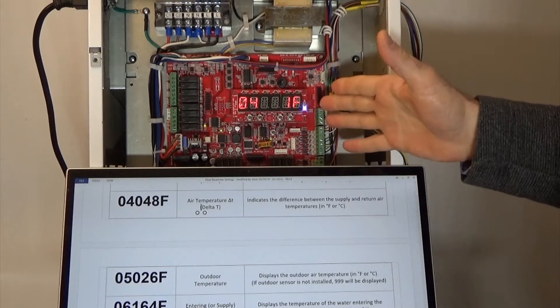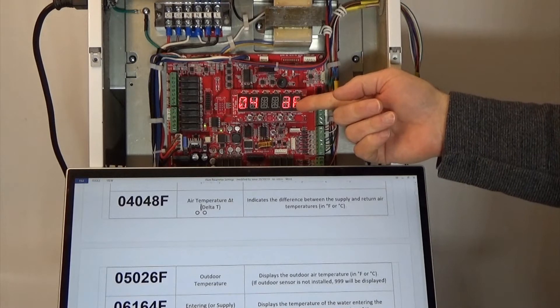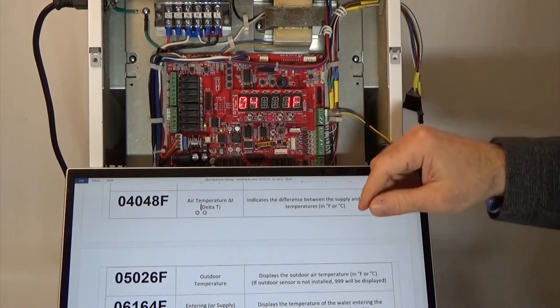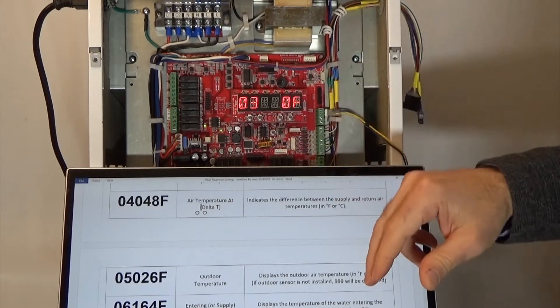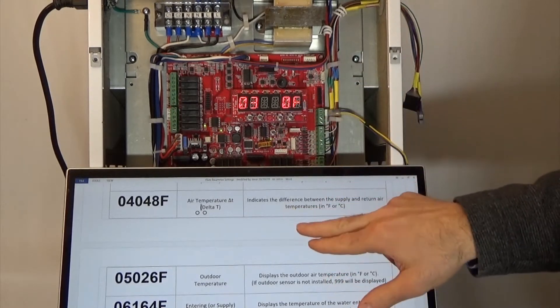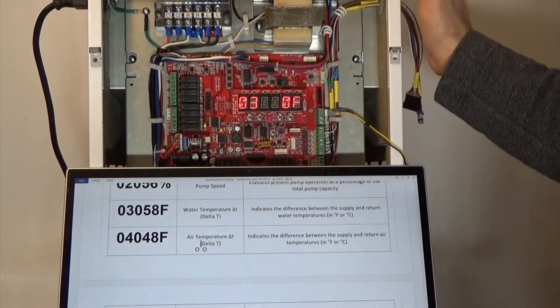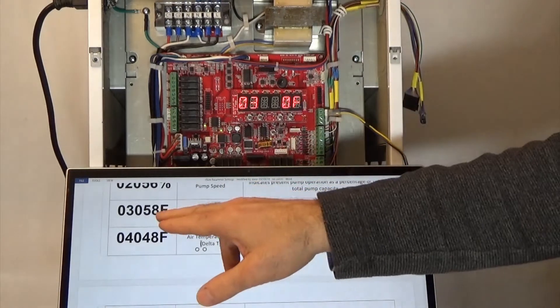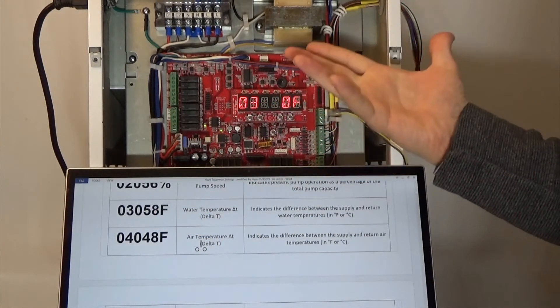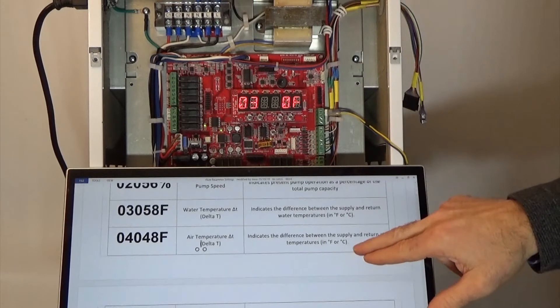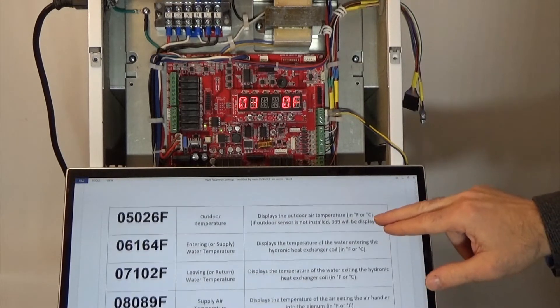Because this unit is off, it makes sense we're seeing zero here — zero differential, both sensors seeing the same number. If we go down to parameter three, same thing on the water side. Because the unit is not operating — this is just a demo unit in the office — we're seeing the differential being zero, which is what we would expect. Both sensors should be seeing the same temperature.